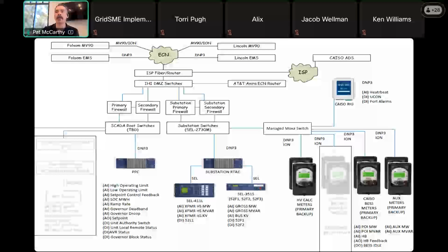So they understand the data path from each originating device up to the rig, and they can ask for all kinds of ad hoc tests to verify data paths and verify that intermediate device configurations aren't misrepresenting data quality. So the accuracy of this document, and keeping it updated as you update your project design, is important. Otherwise, CAISO might get frustrated that you're trying to test a system they never approved.